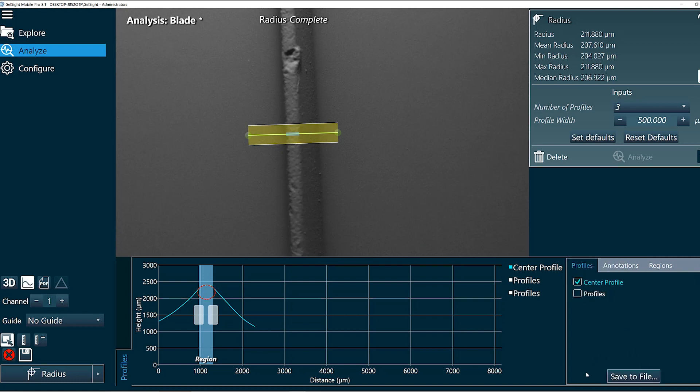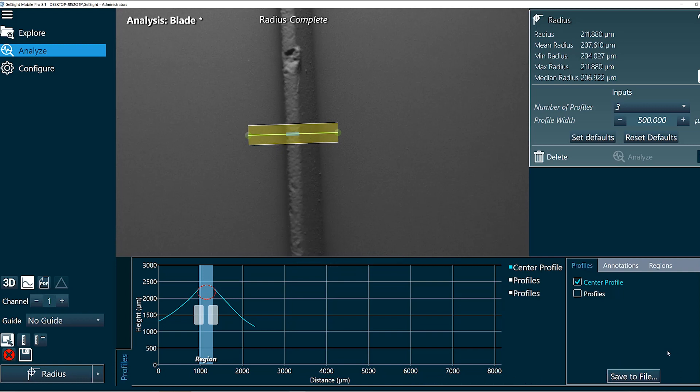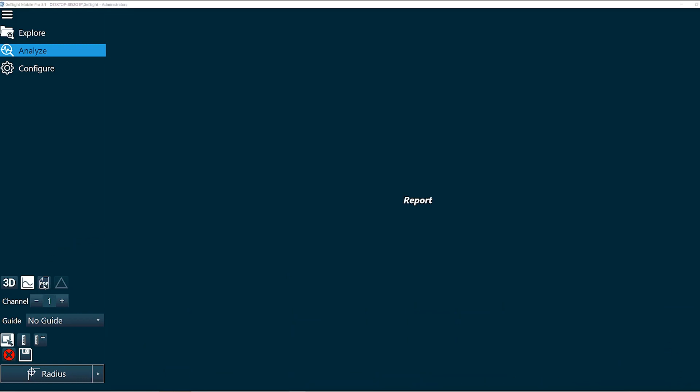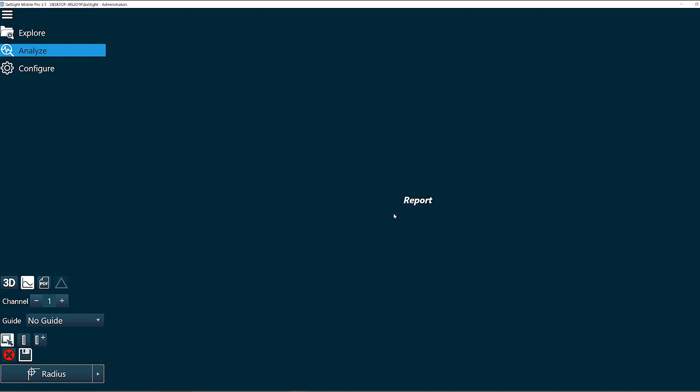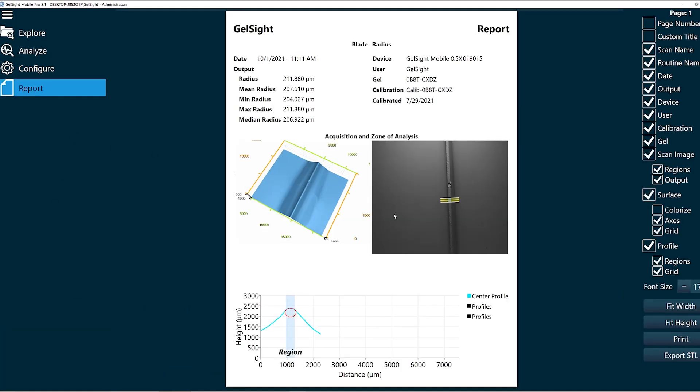If I want to save the data to plot this graph as a CSV file I can click save to file here. And now that I've measured my radius I can click PDF to generate the PDF report results.